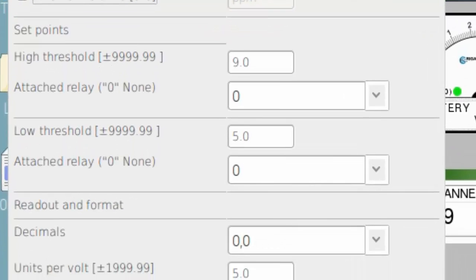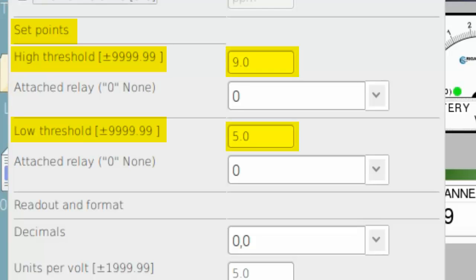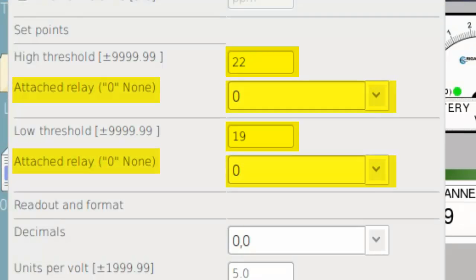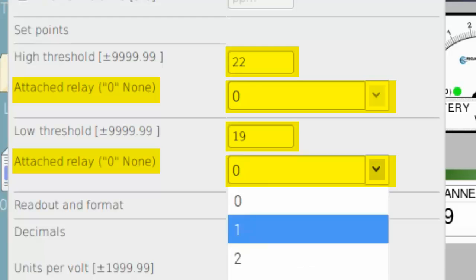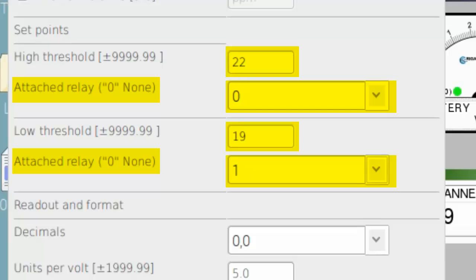Next, there's a section in the dialog box called Set Points, where we can set the high and low thresholds for the channel so that an alarm lights on the display when they are exceeded. We set the high threshold at 22 degrees centigrade and the low at 19. When the temperature drops below 19 degrees, a relay is activated, for example to turn on a heater. We type the relay number we want to activate in the relay box; if we don't want to activate any relay, we type 0. Let's put 1 in the relay box linked to the low threshold, and leave the high threshold relay at 0.